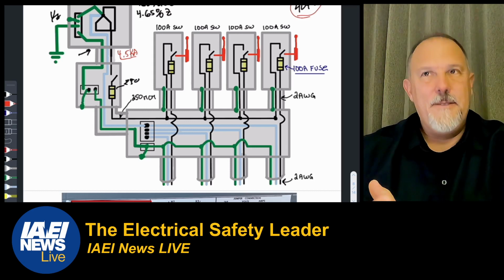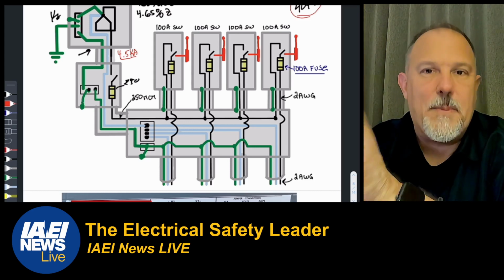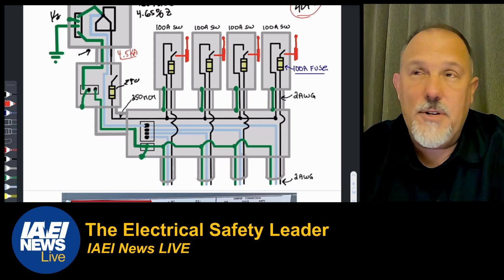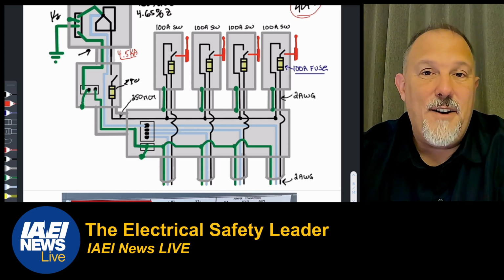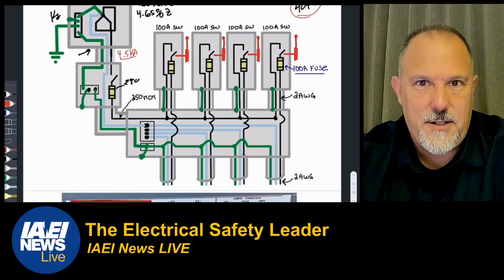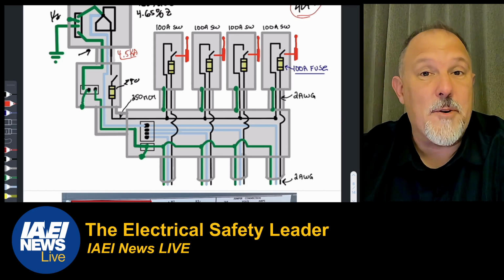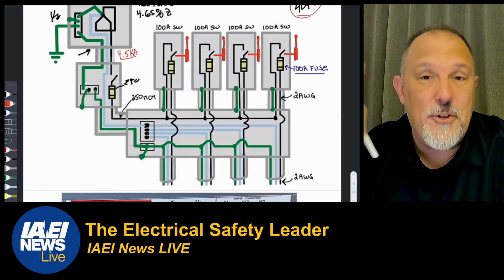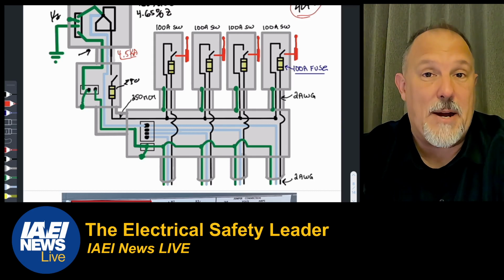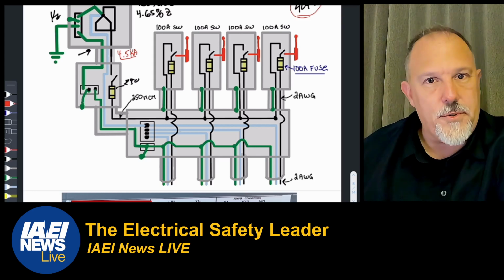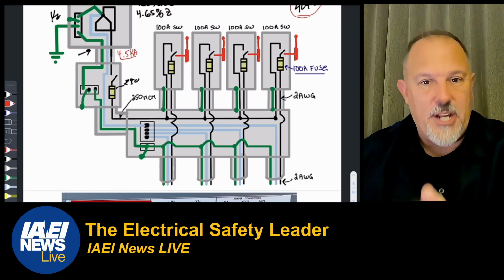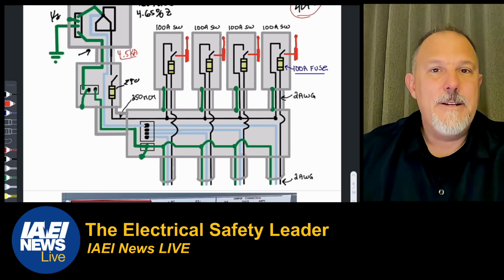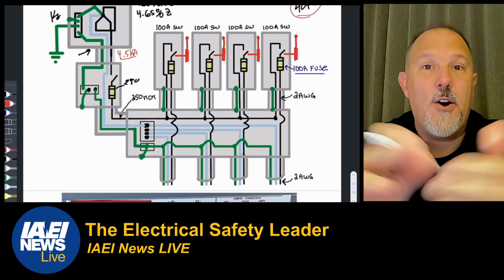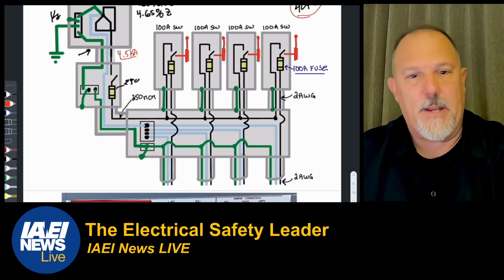That requirement, it was an electrical inspector drove that change, saying he would not permit the use of those occupancy sensing switches, because they would use the equipment grounding conductor. He required you to pull a neutral and properly wire that switch between hot and neutral to power the switch to do your controls. So they changed the National Electrical Code. I can't remember what cycle it was, and if you know, put that down in the chat. Come on, let's make it happen.